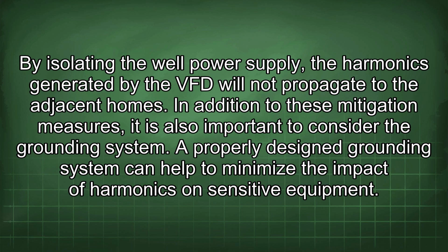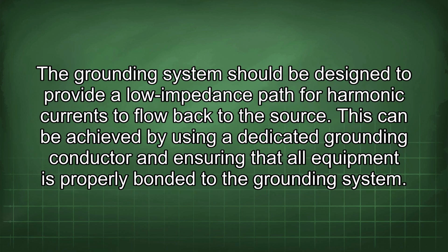In addition to these mitigation measures, it is also important to consider the grounding system. A properly designed grounding system can help to minimize the impact of harmonics on sensitive equipment. The grounding system should be designed to provide a low impedance path for harmonic currents to flow back to the source.